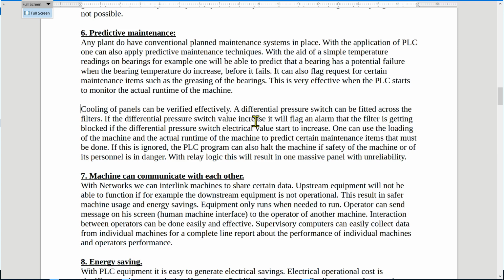Now, one can use the loading of the machine and the actual runtime to predict certain maintenance items that must be done. And the beauty of a PLC is if the operator or the maintenance personnel ignore the warnings of this PLC, we can even halt the machine, especially when the machine safety or the people operating the machine is in danger. Now, with relay logics, this will result in one massive panel with unreliability.